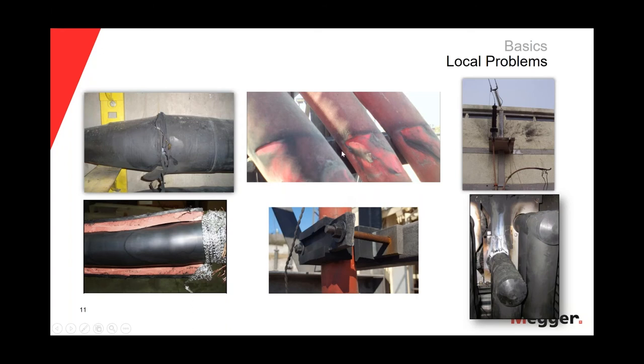Another classic workmanship issue shown is where the guys fixing cables in the holders exceeded the torque and inflicted deformation in the cable, which sooner or later will create partial discharges. The last two pictures show classic termination problems — one where the cuts were not made correctly, and another where contaminants were introduced during assembly. All these are local issues affecting specific portions of the insulation, related to workmanship issues or manufacturing defects.